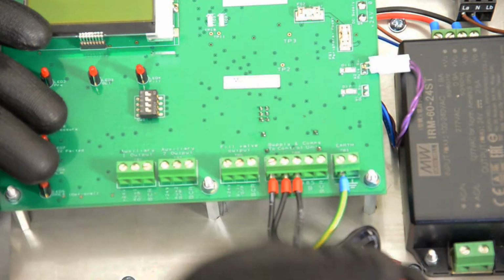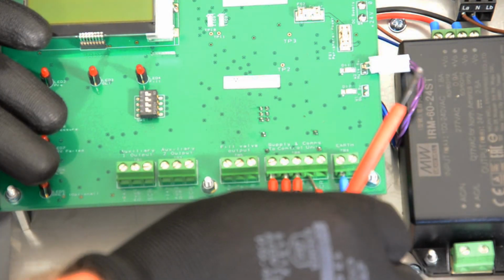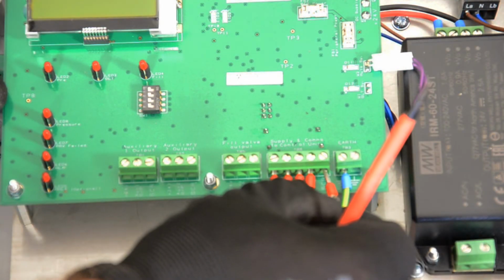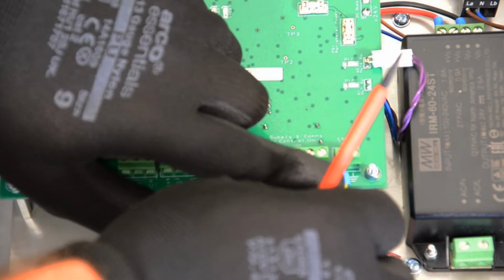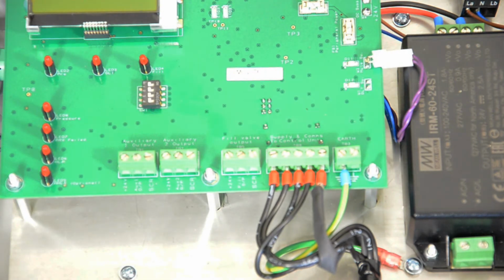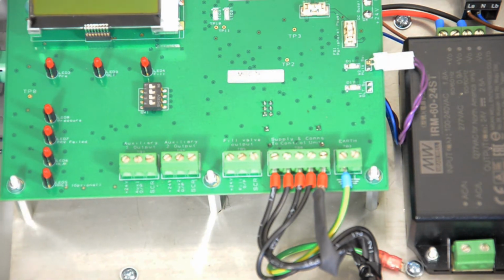On the level probe terminal block, wire 1 goes to 24 volts, 2 to 0 volts. The serial communications wire number 3 goes to RS485A, wire 4 to RS485B, and the screen wire goes to number 5. Run this cable to the top of the silo and duplicate these settings in the PRV control box.